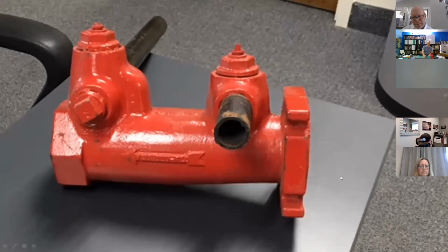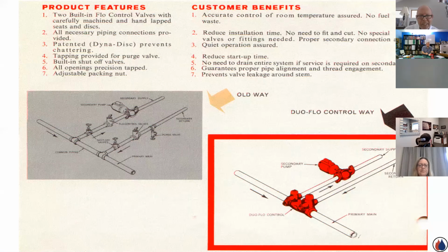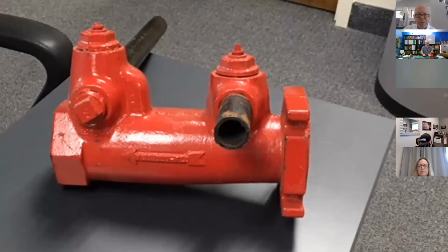This is a quick example. I had only found one. I had an apartment building out in Worcester, Massachusetts that had 24 of them, and one of them had developed a leak. And so it now sits in our education room at FIA in Woburn. To solve the problem, the guys ended up doing kind of what you would have done without those fittings. They just piped in a couple of closely spaced T's, shut-off valves, and flow control valves, and they got the system back in business. And I got one of those fittings to sit in our education room.